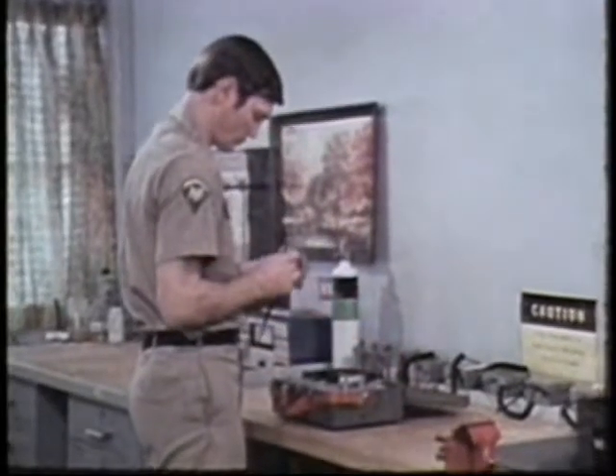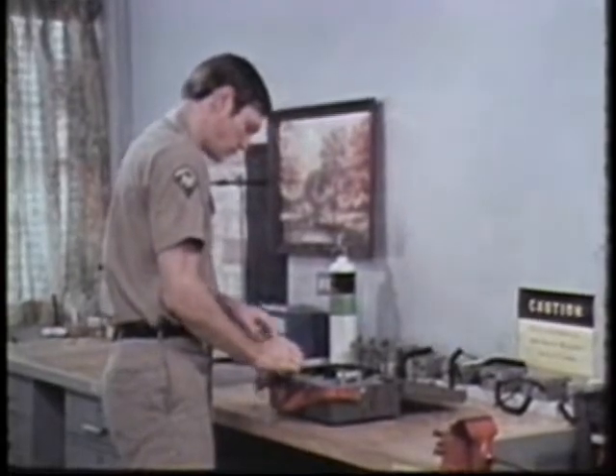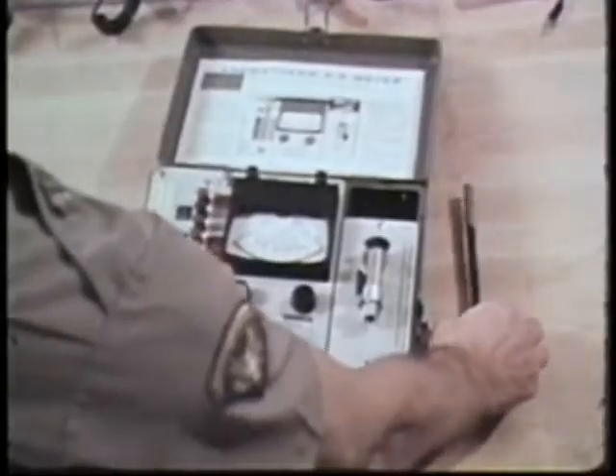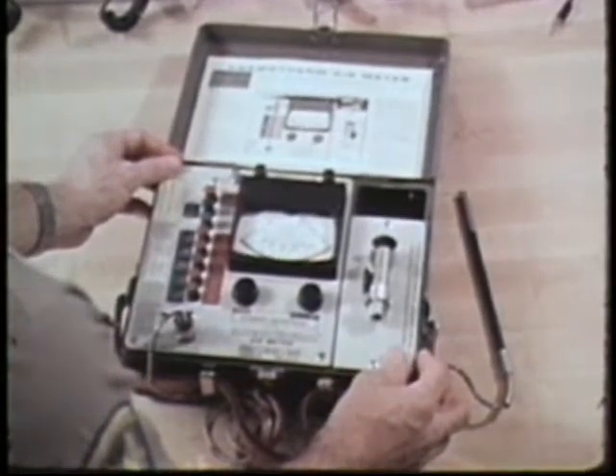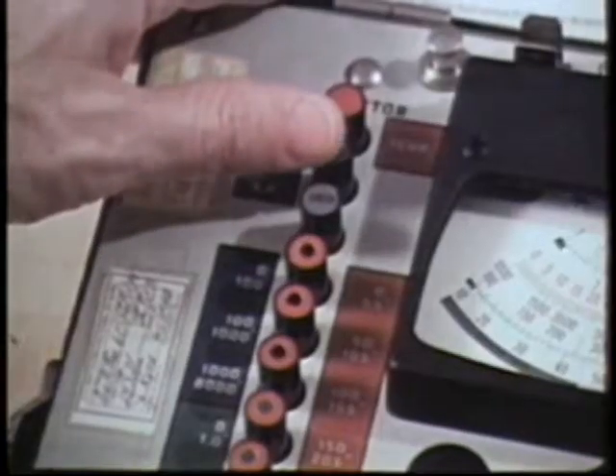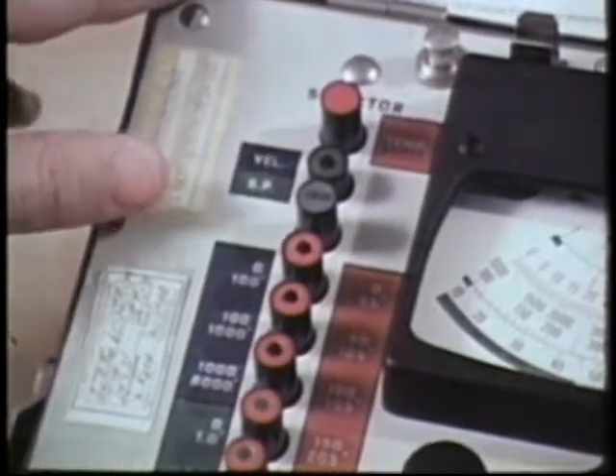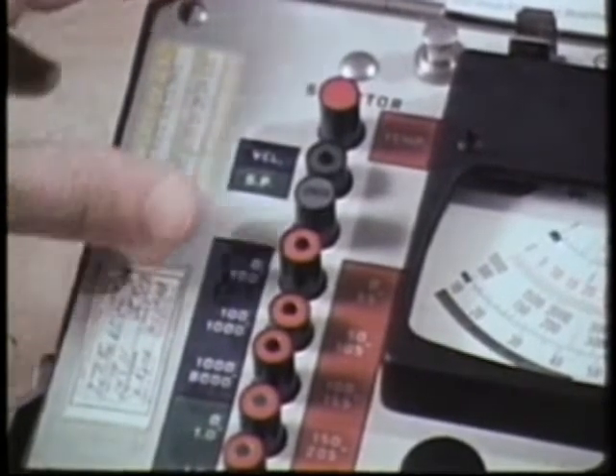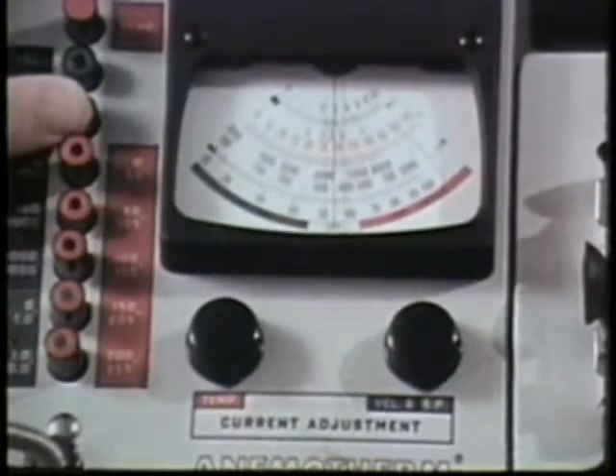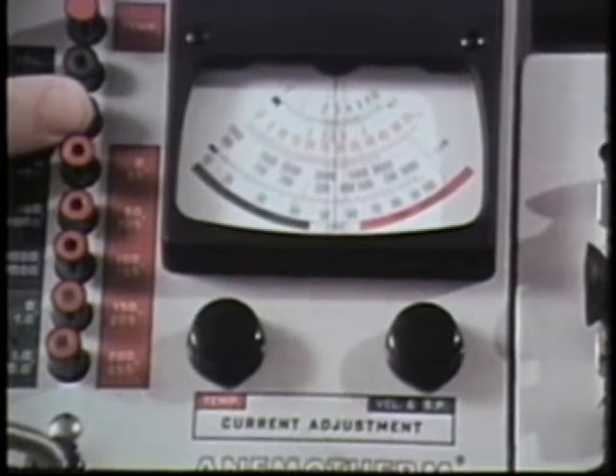First, the anemometer or air velocity meter. To adjust the calibration, select the velocity and static pressure mode and the 100 to 1000 scale. Then hold down the check button. The needle should swing and stop exactly over the red calibration mark.